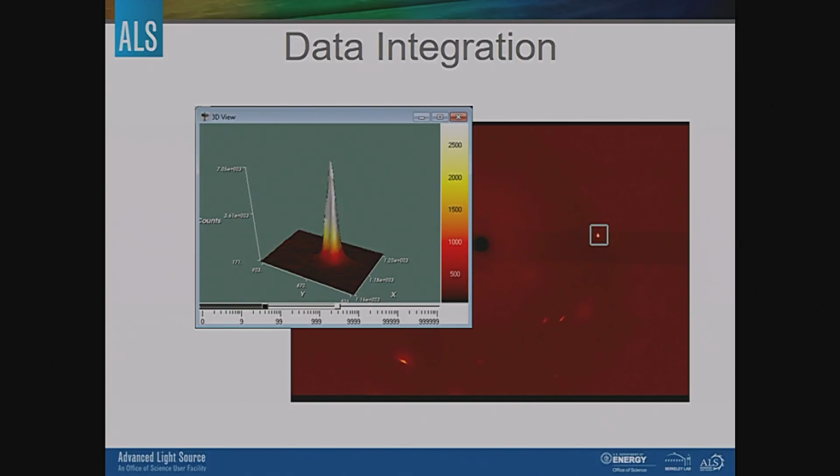There's a lot less work in estimating the intensities, because with this detector, the X-rays come off the crystal, hit the detector, and hit a phosphor. This phosphor converts X-ray photons into light photons, and then that goes on to a visible-light-sensitive sensor. So there are a lot of conversions you have to work in. Now the new fast detectors, like the Pilatus, are direct detection. They just detect the X-ray photon. Oh, you have an X-ray photon? I'll count it. That's all. So it's getting a lot easier now to do intensity integrations, instead of having to say this phosphor makes this many visible light photons for this many X-ray photons. You don't have to do that as often anymore, which is nice.